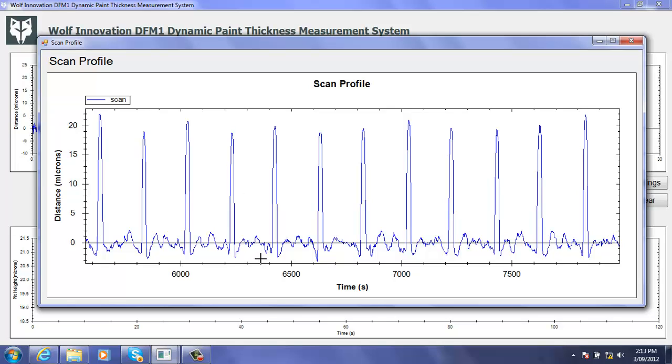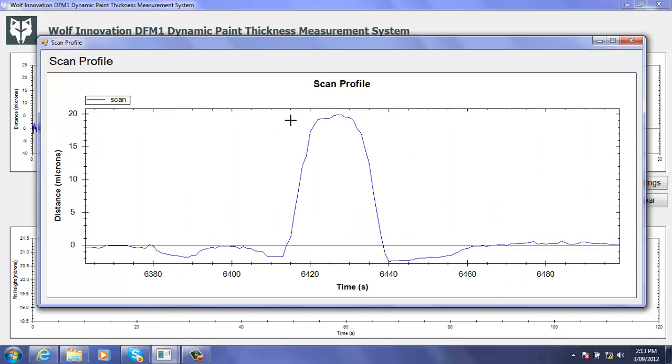Here we're looking at the many measurements that make up one reading, one thickness reading, consisting of the surface of the painted steel and the bottom of the little micro pit.